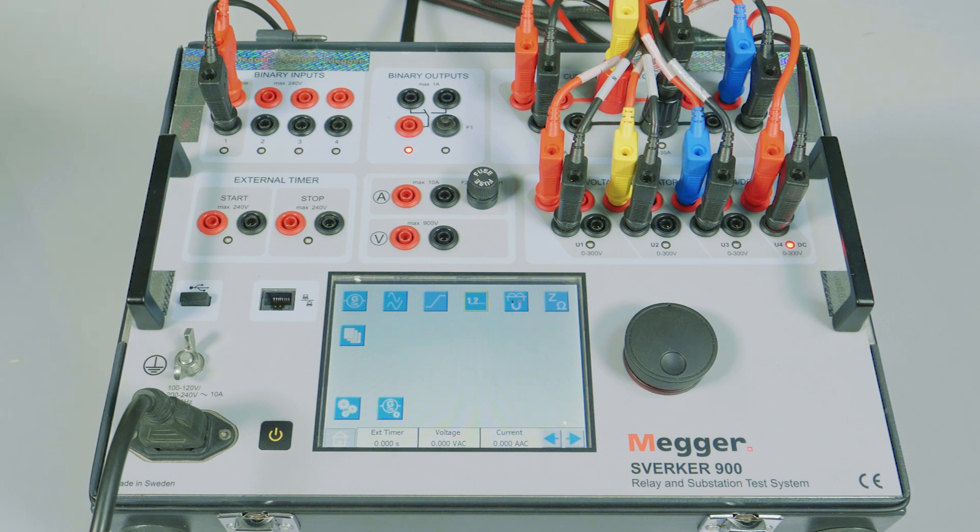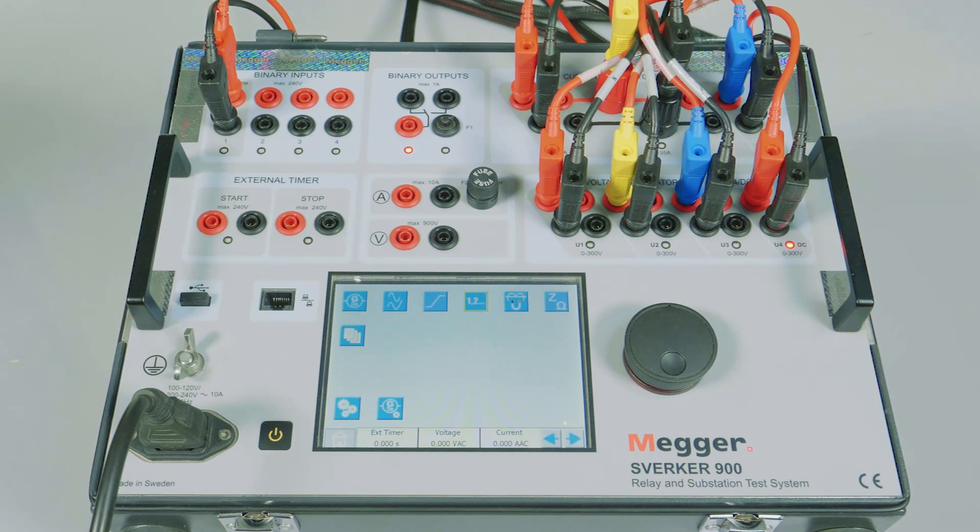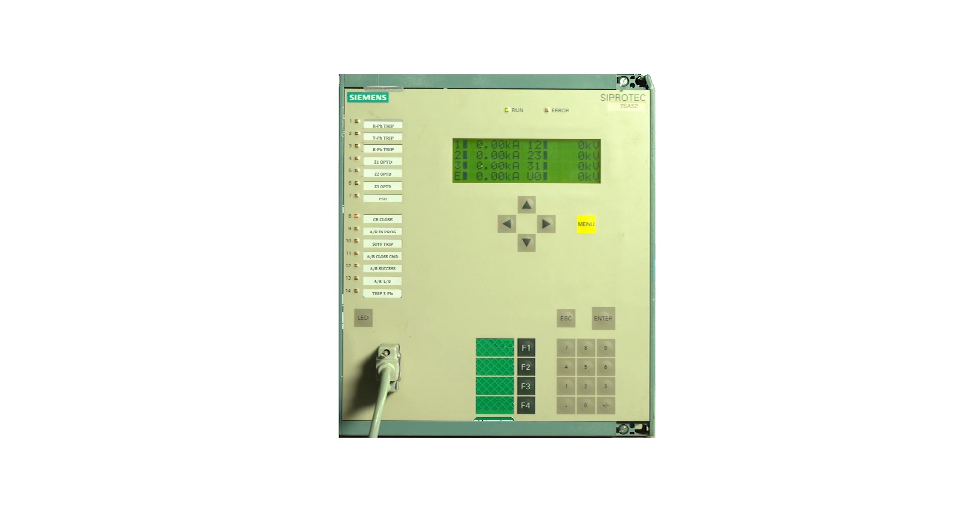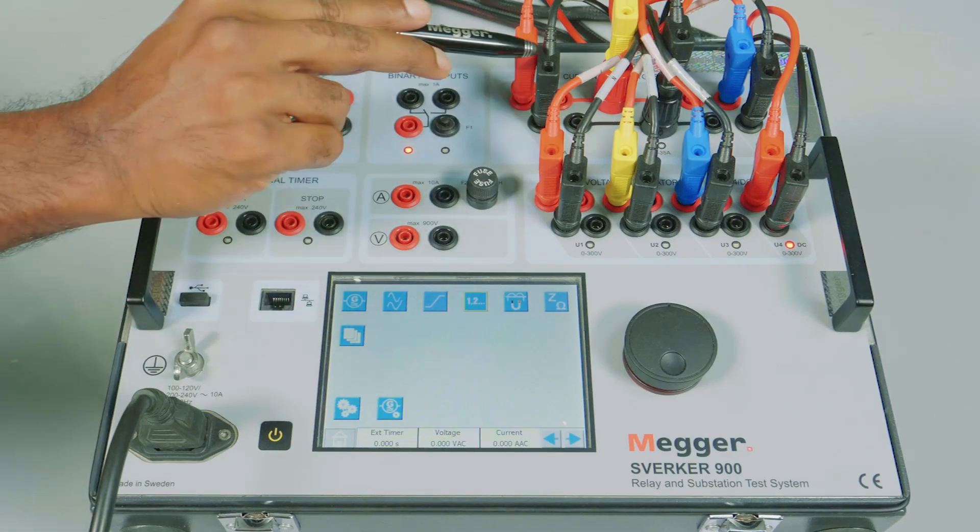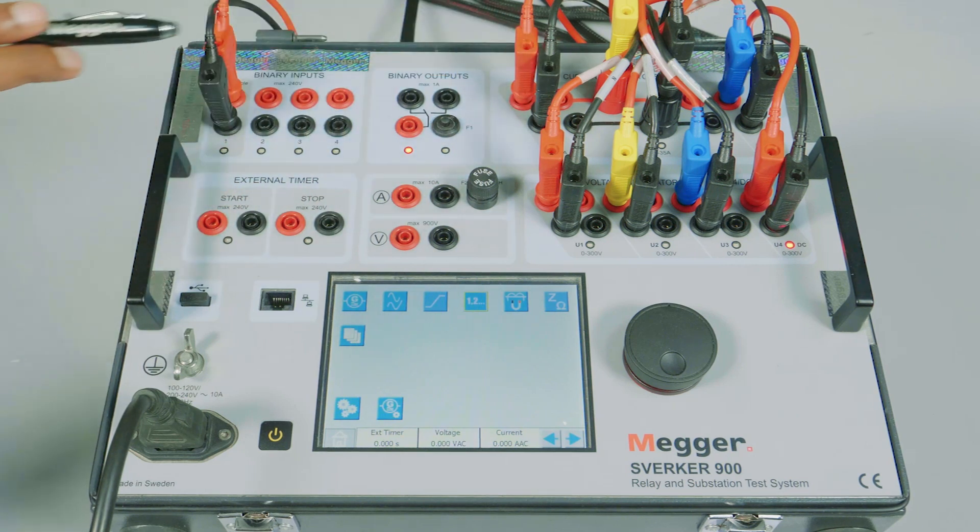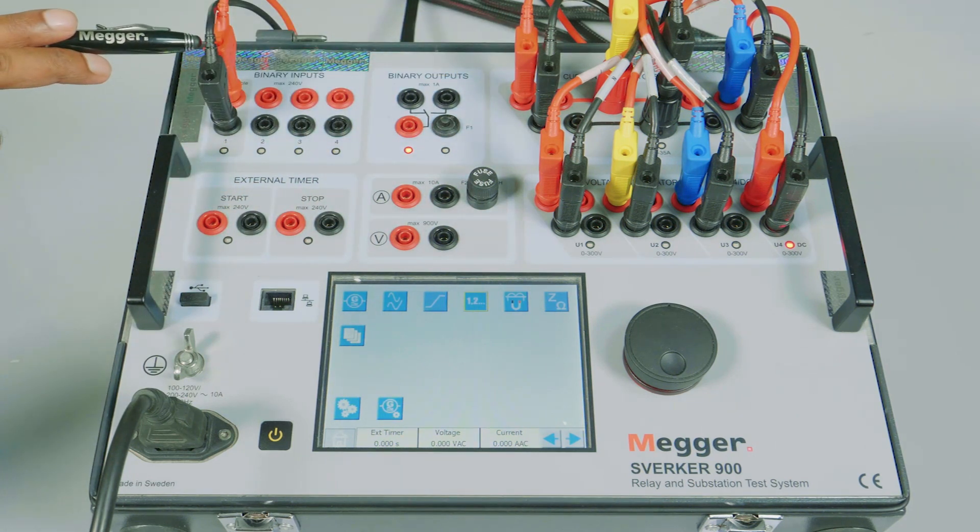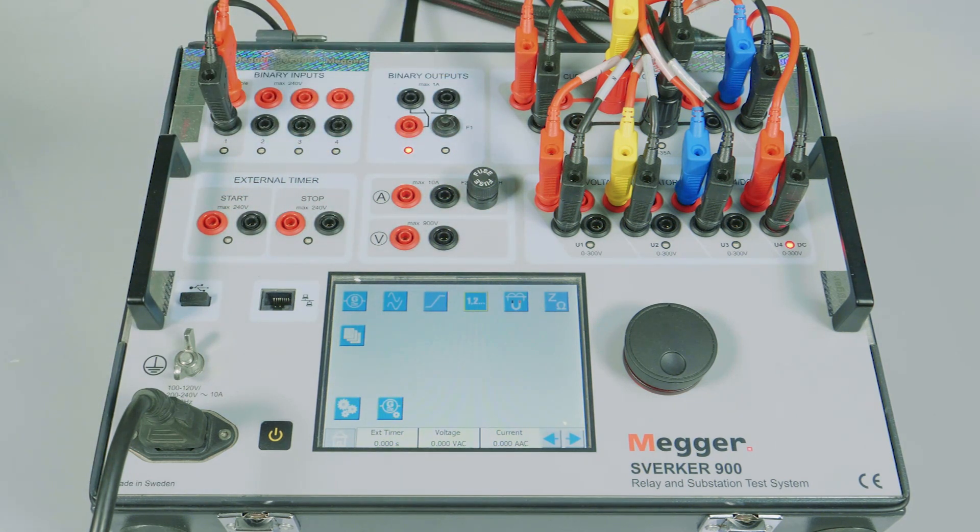Successful auto recloser. SVERKER 900 test kit is connected to a Siemens 7SA52 distance protection relay. The CT and PT is connected to the relay and the TRIP feedback is connected to binary input 1.